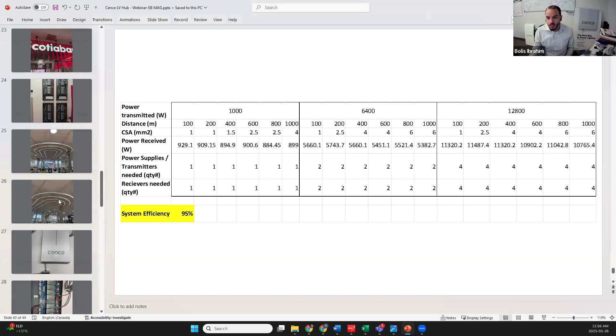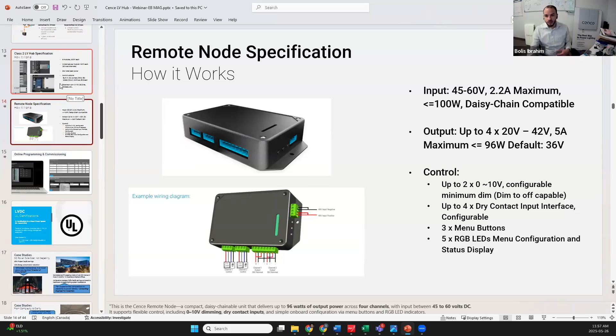Most of what it is, it's about controls. So if it's UL 924, what you've got to do on the remote side is make sure you have an emergency-rated controller. It's more about the controls, about what happens in the case of an emergency. For example, there's a dry contact, and as long as your system can take a signal from, say, the fire alarm or the emergency lighting inverter, it can take that signal and go into emergency mode, where only the emergency lighting comes on and everything else shuts off. Then yes, you can get compliance for emergency.